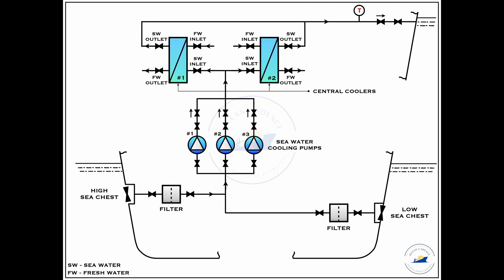By doing so, what we are analyzing is the temperature difference between the inlet and the outlet of the sea water circuit, and by doing so we are also gauging the efficiency of the cooler. The temperature gradient gives us an indirect hint towards the efficiency of the cooler. As we know that in its optimum condition, the cooler is supposed to maintain a certain temperature gradient. By comparing the gradient that is available to us through the readings and the one that is suggested by the maker in the manual, we get to know what is the condition of the cooler.